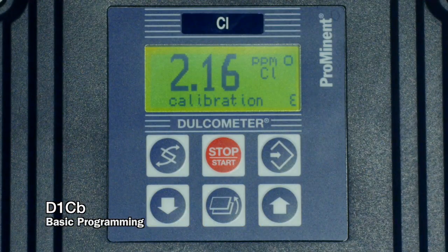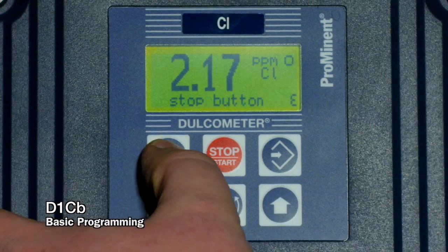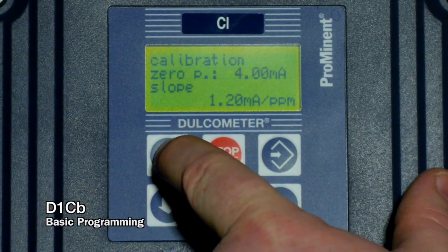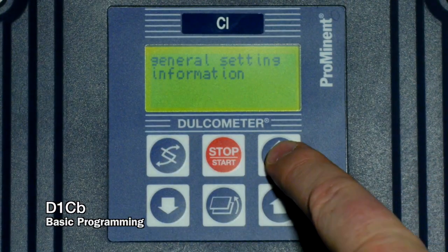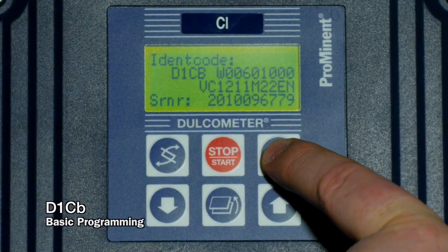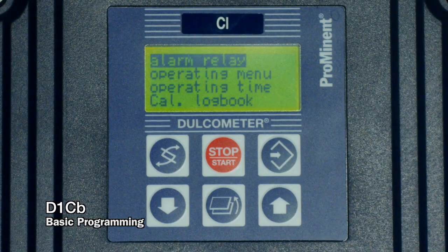This section of the video is to show some of the programming setup on our D1C-B. This is different from the D1C-A, so be sure to check which model that you have. The first thing that we need to program into the unit once we have wired up the sensor is to match the sensor range and the type of sensor to the controller that we have. To do that, we'll hit the change key until we get to general setting information. We hit the enter to enter this menu and scroll down through. We're going to scroll down until we get to where we can make selections.